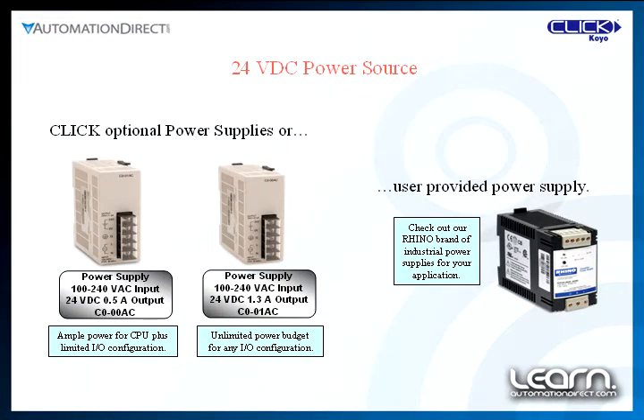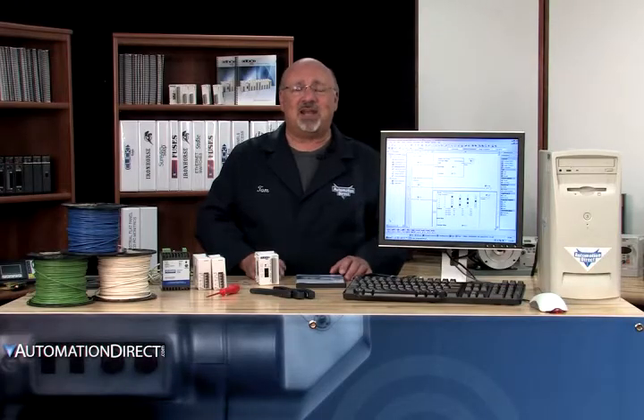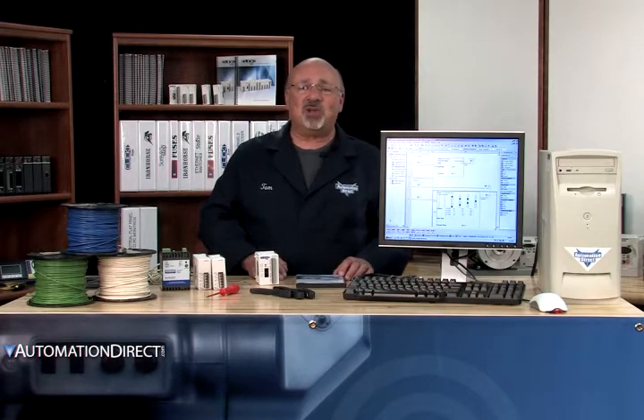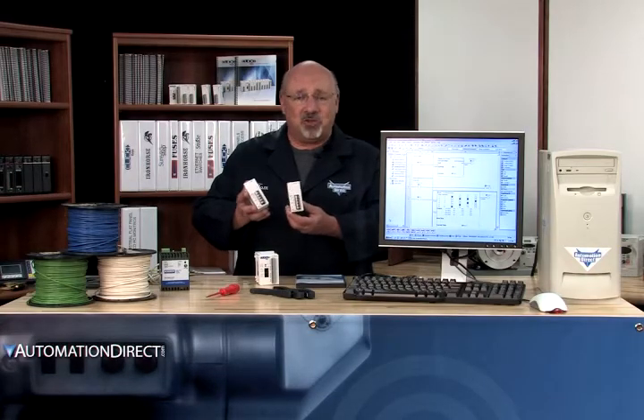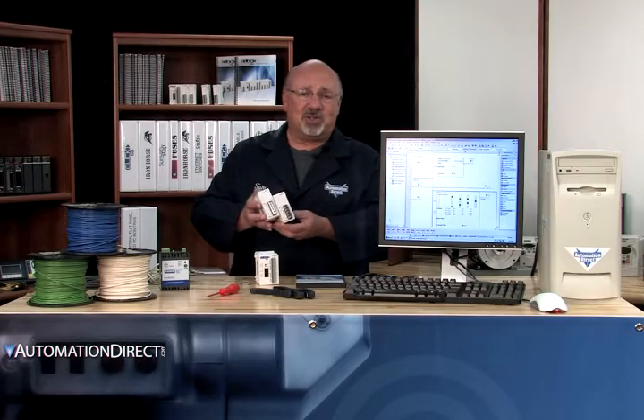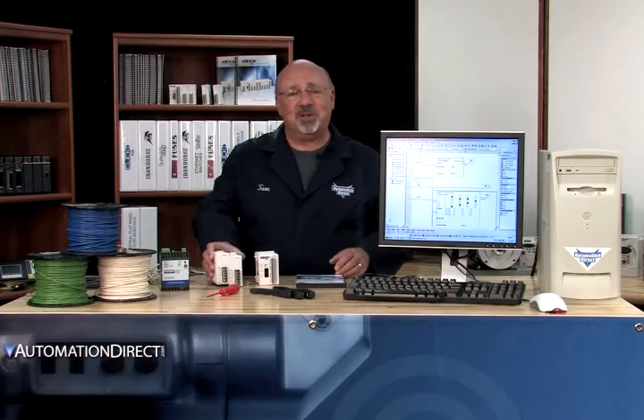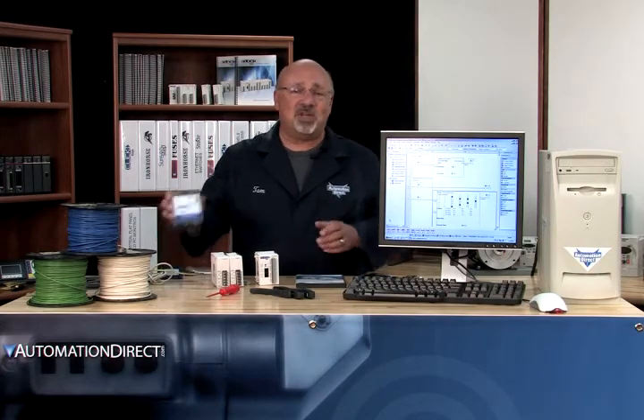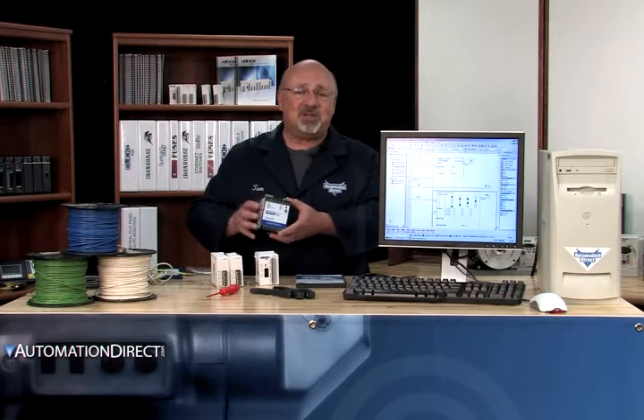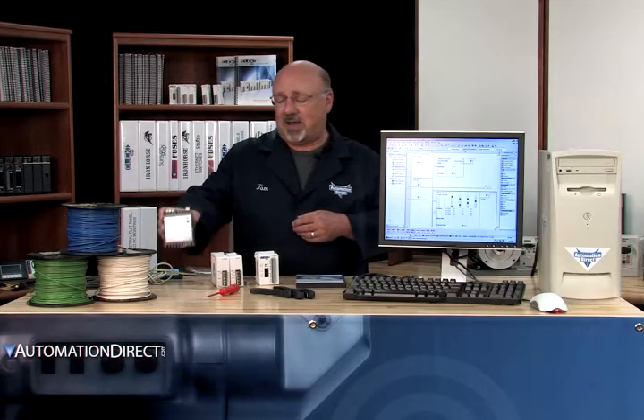We have a couple of choices here. If you already have a 24 volt DC power source with good regulation and at least 120 milliamp capacity — 180 milliamp for the C0-00DD1-D CPU — you are all set. The other choices are to use one of the optional CLICK 24 volt DC power supplies, or to purchase a 24 volt DC power supply such as the Rhino series offered by AutomationDirect.com.